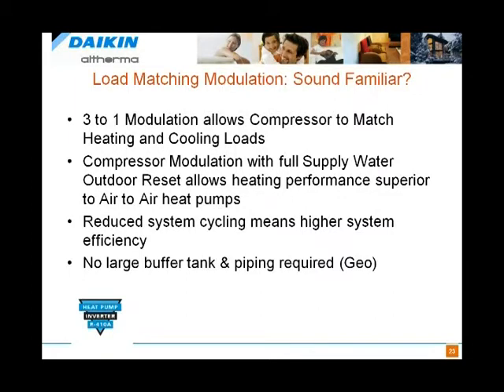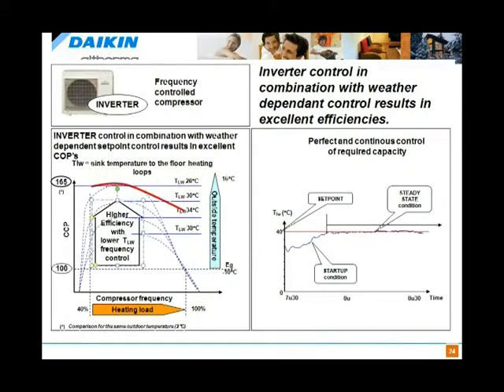Of course, with modulation, we reduce system cycling, which means overall system efficiency is higher, as well as the need for the big buffer tanks that you're familiar with from geothermal on-off heat pumps. The few on-off air-to-water heat pumps that have been available aren't required, and frankly cut a lot of cost and complication out of the systems. So this is just diagrams showing the load matching characteristics, particularly in relationship to outdoor reset, that are so attractive.